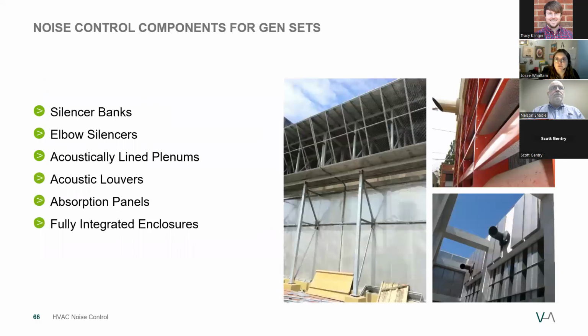Potential noise control solutions for generators are intake and discharge silencer banks, where the dimensions will vary based on performance and space restrictions. Elbow silencers could be used in tight spaces. There could be acoustically lined plenums. Acoustical louvers can be used, which can vary from 4 inches to 24 inches deep. Absorption panels could be installed on interior or exterior walls. And finally, a fully integrated enclosure.